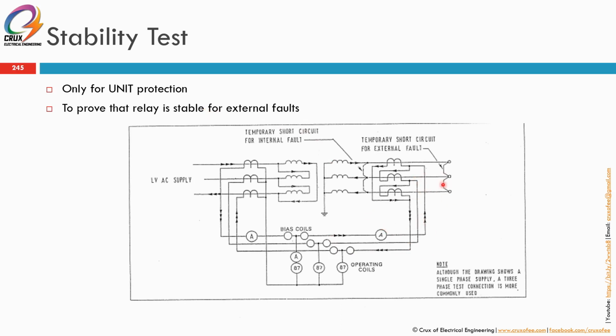So what you do is you inject the CT, you inject the primary side. You need to bypass here, because the primary injection cannot push the current through the winding. The winding is too high impedance for the primary injection test set to push the current through. Even though the current coming out of the primary test set is 800 amps, 1000 amps, the voltage across it is very small, maybe 10 volts, 50 volts or so. So if you want to push that current across an 11 kV winding, that will not be possible. That's why you have to short at the transformer terminal.